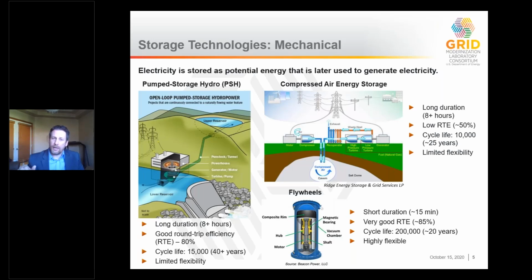The first two, pump storage hydro and compressed air energy storage, are long duration technologies. These can be constructed to do 8 hours or more of discharge, especially pump storage hydro. Pump storage hydro has a better round trip efficiency—how much energy comes out relative to how much we put in—and a very long cycle life. Both technologies, though, aren't very flexible. They can't respond to those momentary changes from one moment to the next in the grid, things like frequency regulation.